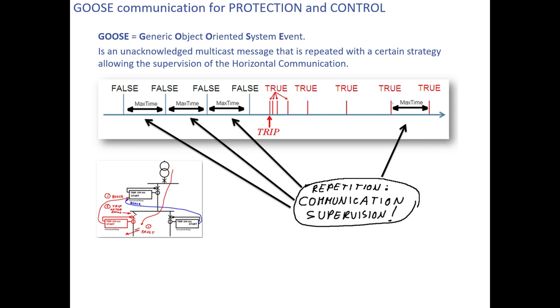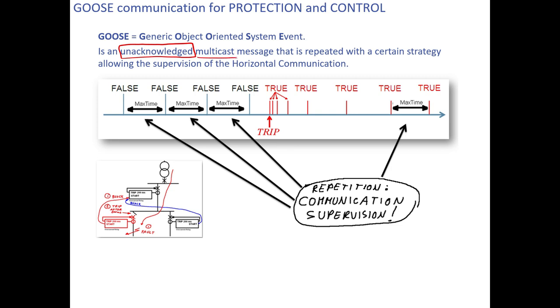The first topic is GOOSE communication for protection as well as for control. GOOSE means Generic Object Oriented System Event. GOOSE is an unacknowledged multicast message — that is a keyword I will explain — repeated with a certain strategy, allowing the supervision of horizontal communication.